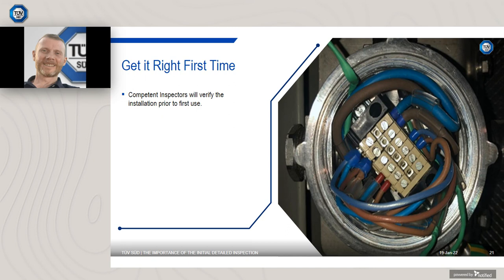Competent inspectors will verify installation prior to first use. Having inspections carried out by competent inspectors is belt and braces practice. The installation in the photo was a 240-volt lighting circuit internal to a package due for shipping to a major project. The supplier had mistakenly identified the fire barrier on a fire-resistant cable as a screen.